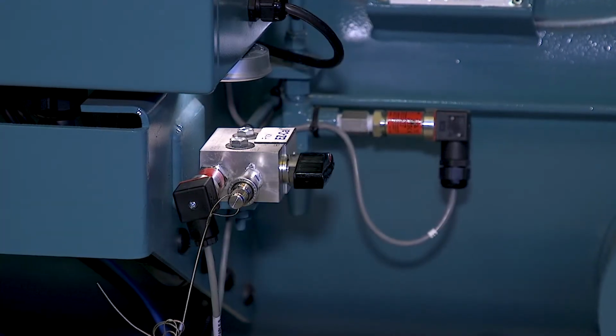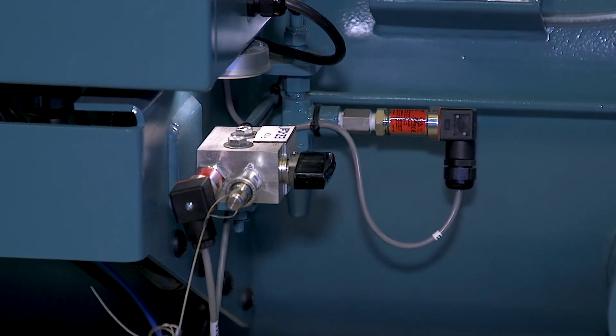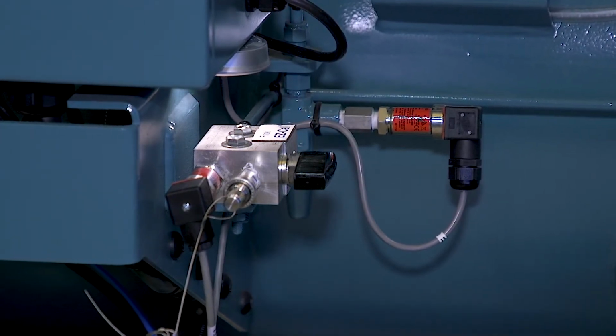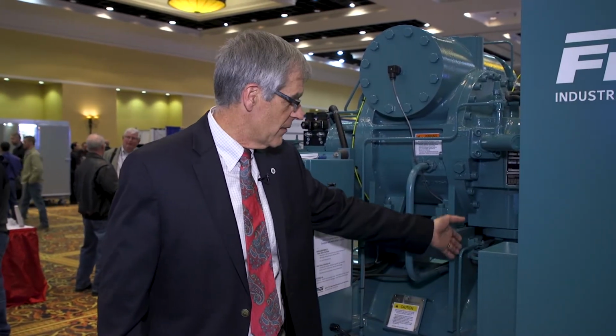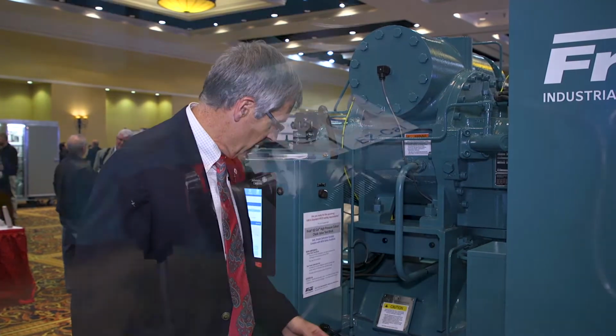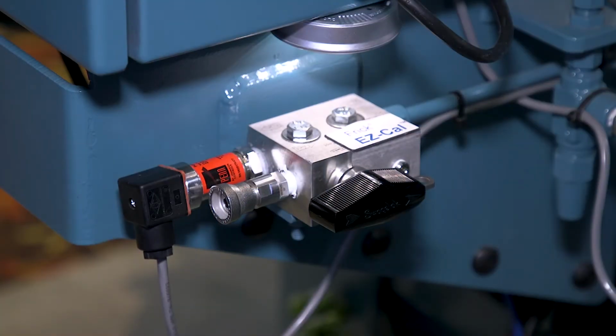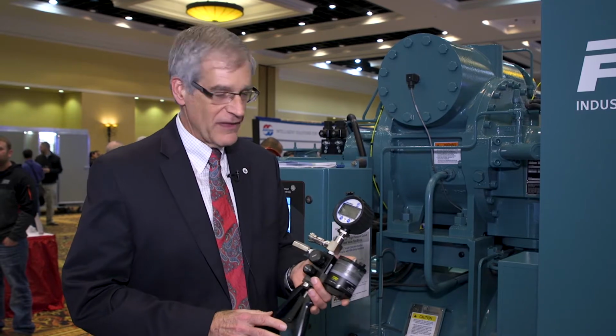I can show you there's basically two components to it. We have a calibration block that would be fitted onto a compressor package. So the block goes between the discharge pressure source, which would typically be coming off the discharge line of the compressor, and the transducer that forms the high pressure cutout. So we have basically a hand oil pump that we're going to use in order to test the high pressure cutout.